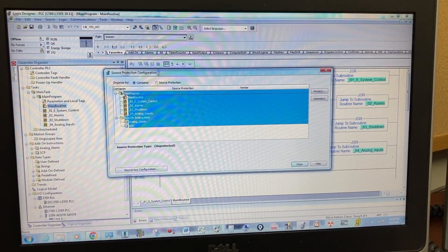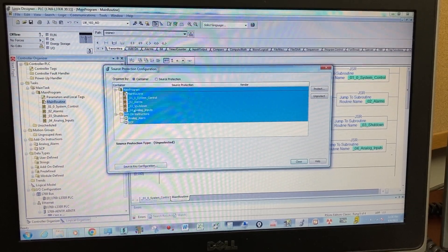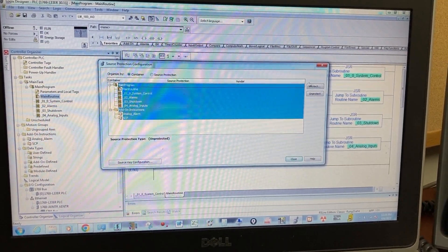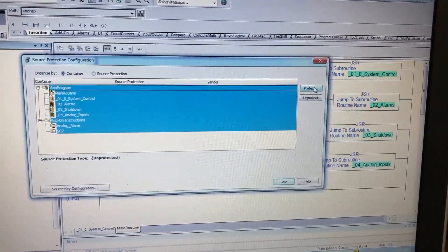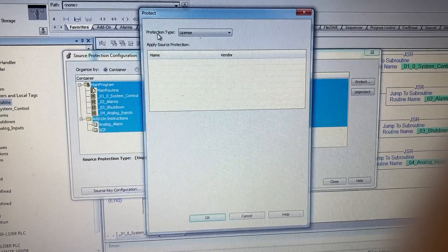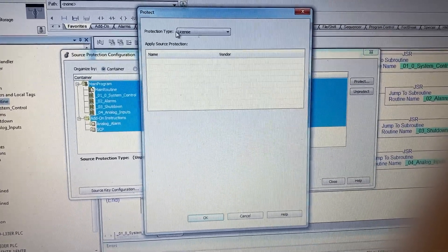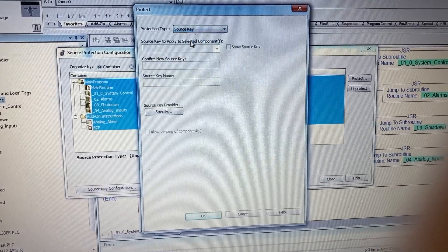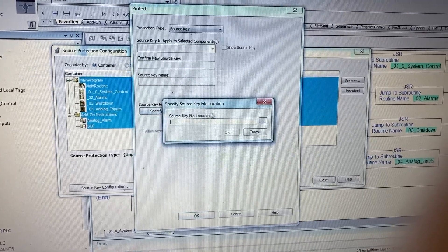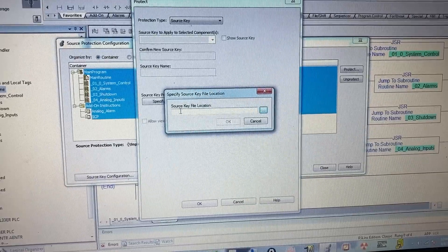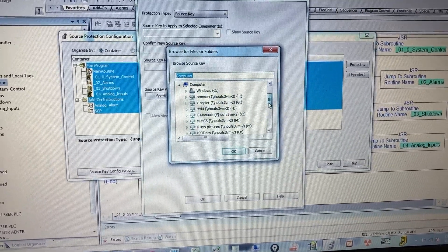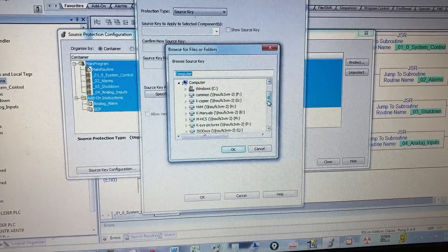Hold CTRL to select both the main program and add-on instructions. Select Protect. For Protection type, select Source Key. Click Specify, and for the Source Key File location, browse to the location where you want to save the source key.